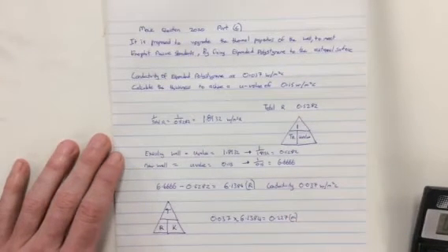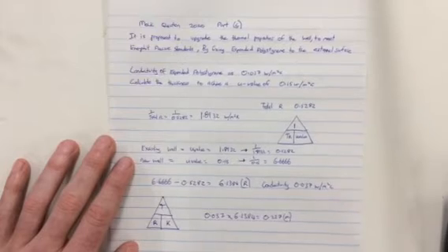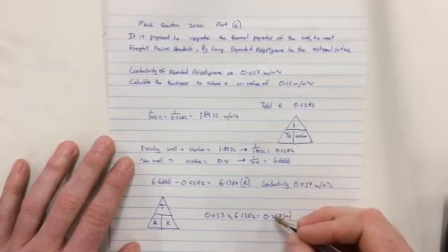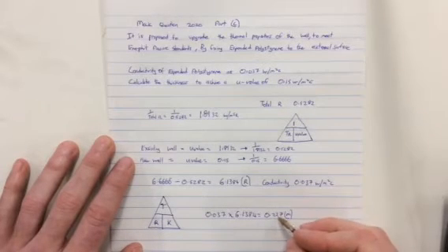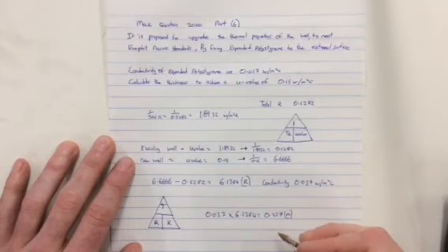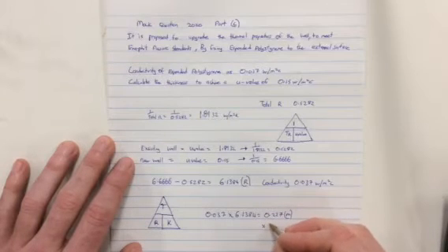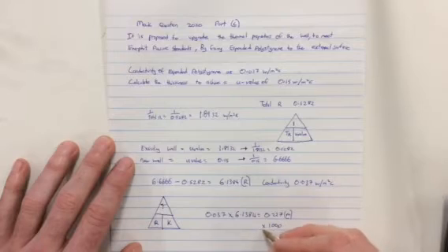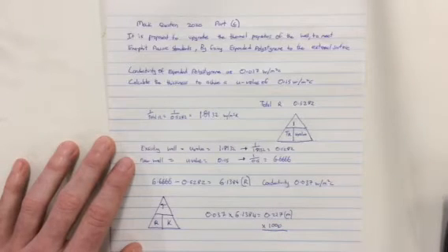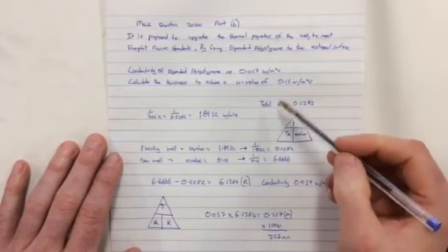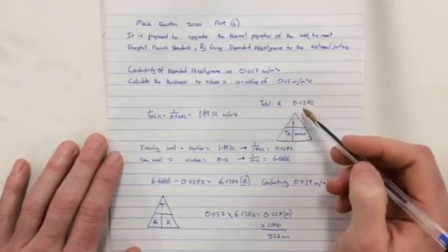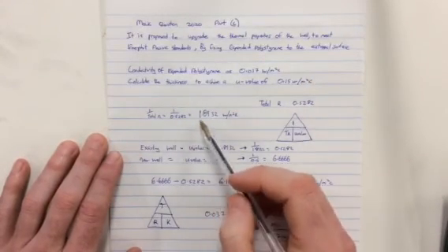When we are starting off doing our U-value question in our table, what we usually do is convert our millimeters to meters for the purpose of the calculation, because it's meter squared. So now that's 0.227 meters. If I want to put that into millimeters, which I do, I'm going to multiply that by 1,000, and that gets me 227 millimeters. That's the measurement for the insulation required. Hopefully that was where you would finish off at the bottom of your table. You do your calculation as normal to get your U value.